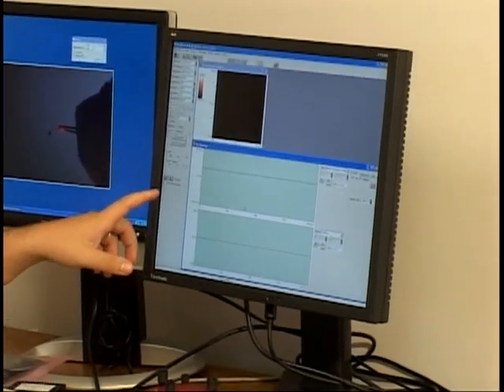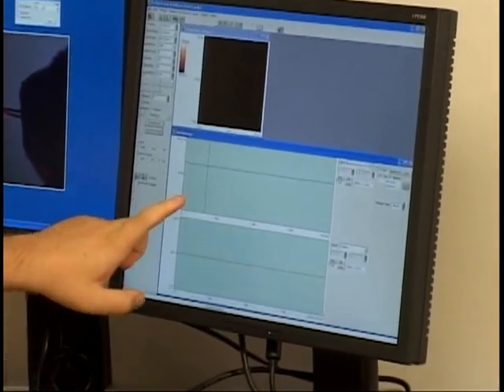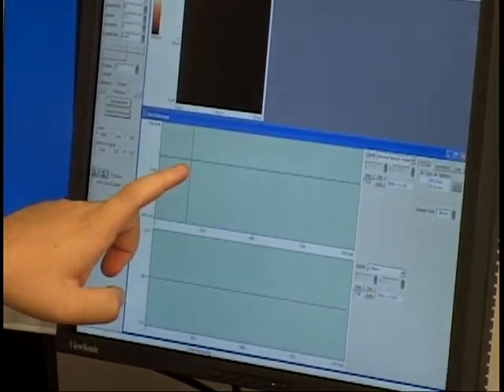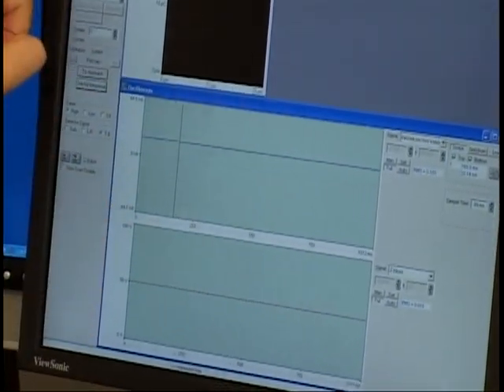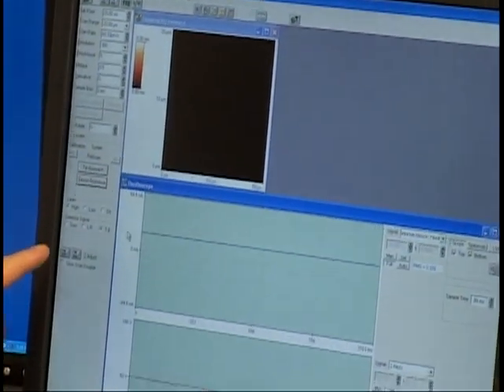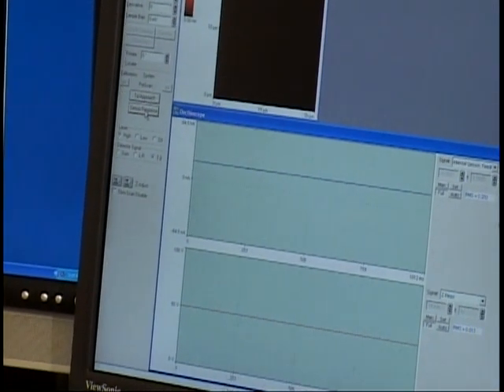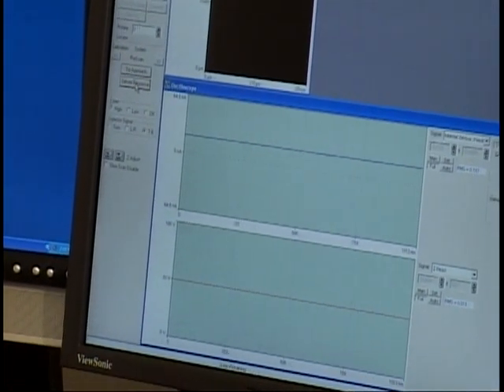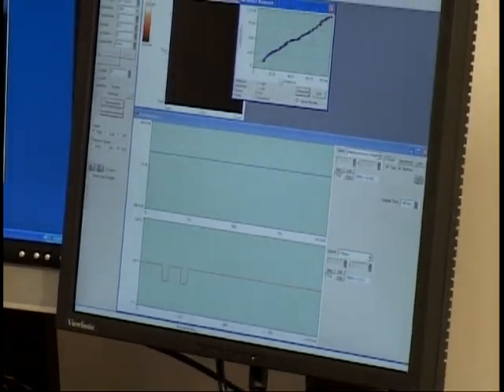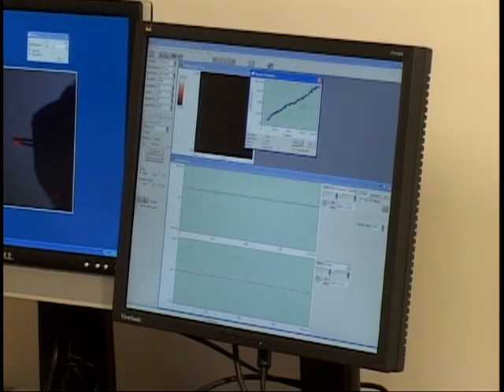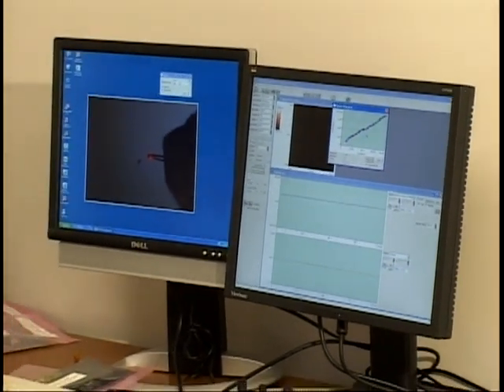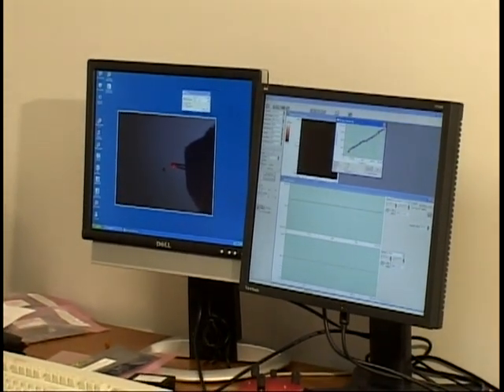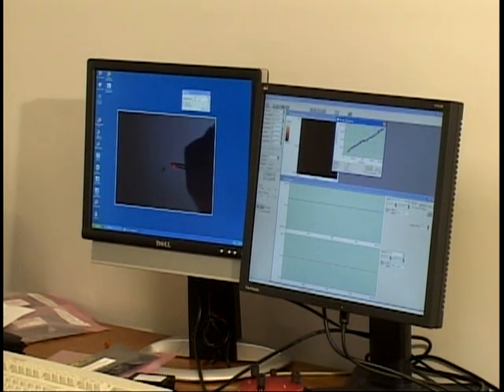After you see that it's engaged, you'll see that it'll be reading 20 nanoamps on your top bottom signal, same as your set point. Then do a sensor response to make sure that you are actually in feedback. Click on sensor response, which is right below tip approach. You should get somewhat of a linear relation. If you do, then you are in feedback. Click exit.